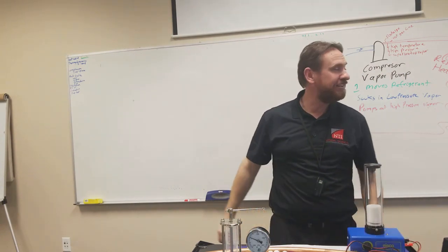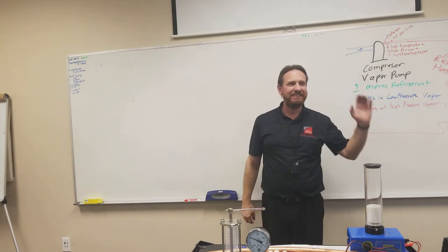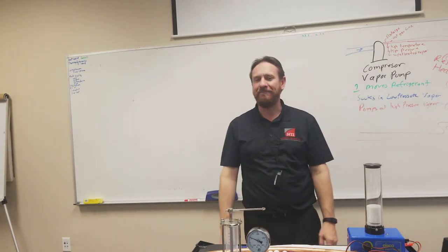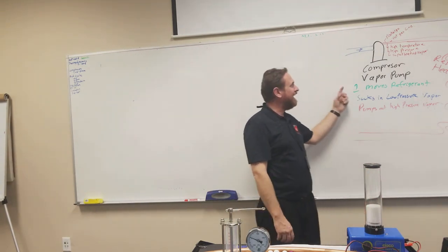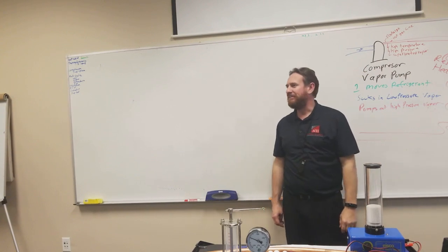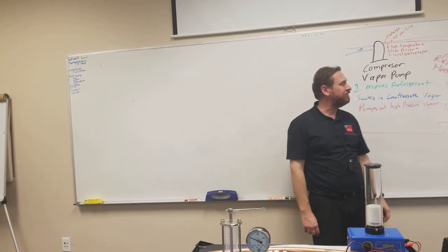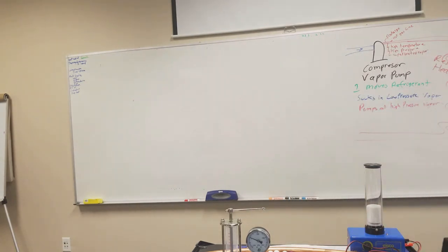So where do you think the condenser is going to be located? Outside. That's exactly right. Rejecting heat outside. When you looked in that box, you saw the compressor in the center, but on the outside of that box, all around it, that was your condensing coil. It's pretty much just a bunch of copper tubes with aluminum stuck to it to increase surface area.